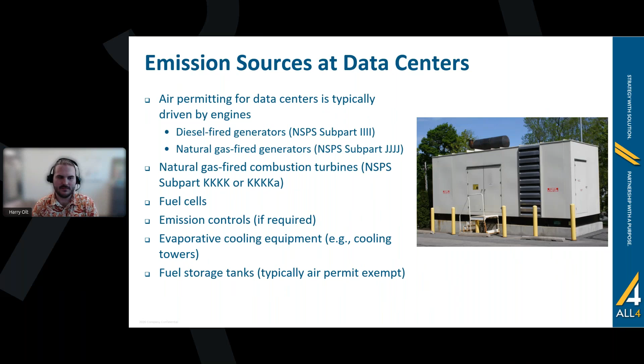So now that we know what is being permitted at data centers, what are some of the early permitting considerations to keep in mind? Many factors can affect air permitting, but considering air permitting early in the planning process can affect aspects of the project. The size of the data center will have a major impact on air permitting, as that typically directly correlates to the number of emergency generators required. Whether the data center is located in an area designated as in attainment or non-attainment with the NAAQS impacts the major source thresholds, which in turn impacts the evaluation of the operating limits and/or emissions controls required to be a synthetic minor source.